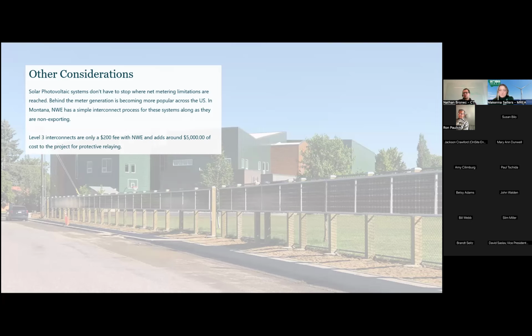We'll be generating more power throughout the day than the building needs, but we aren't exporting that power. We're storing it in the batteries and discharging them at a set, determined time, basically with the battery management system. Often, if it's a residential building, for example, peak loads are at 5 or 6 o'clock at night when people get home and start cooking dinner. Commercial buildings typically peak throughout the day instead.